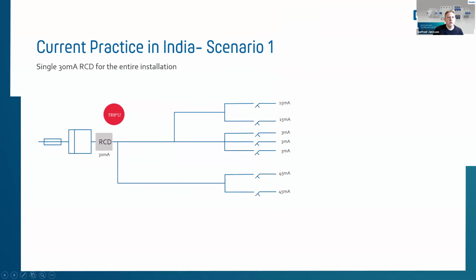Yeah, this is the slide which Krish already explained a bit in his text. If you take a single RCD for an entire installation or for a single house, here for example a 30 milliamp RCCB for personal protection, you would have the risk of instantaneous trippings. If you see the different lines downstream of the RCD, the lines showing up here, 1, 2, 3, 4, 5, 6, 7, 8, those residual currents will sum up in the end. So 15 and 15 would even be enough to trip the 30 milliamp RCD, which will trip at at least 22 milliamp of residual current. So a single RCCB for an entire installation is not the best solution if you do not want instantaneous trippings. So what other possibilities or scenarios do we have?